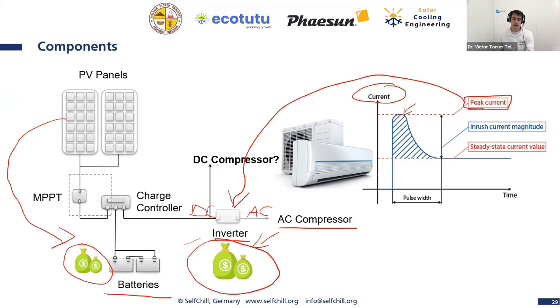We could use a DC compressor. Yeah. This would allow us to get rid of the inverter, right? This will save us money here. DC compressors, DC heat pumps are normally a little bit more expensive, but then you save a lot of money on the inverter. That's why we use DC compressors, DC cooling units, because we don't want to have to deal with an inverter for our cooling systems.